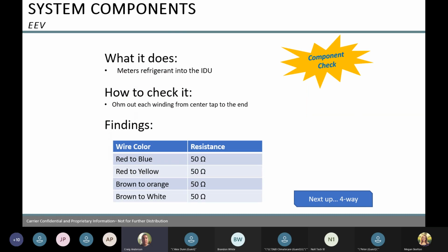So how do we check it? As I said, it meters the refrigerant to the indoor unit. We ohm this out as well, between red and blue, red and yellow, brown and orange, brown and white. Same thing, we're looking for resistance that's equal. So when we're dealing with DC voltage and windings and things like that, we're always looking for readings that are equal to each other or just off a little bit.